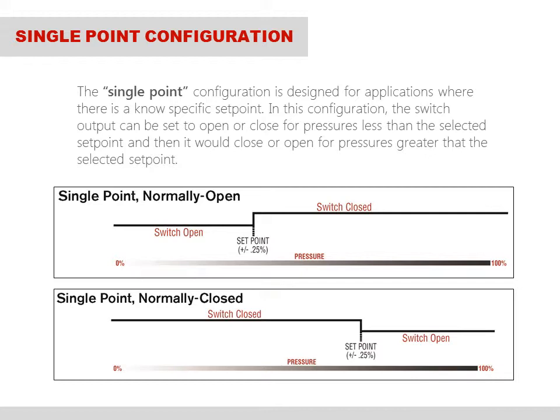The single point, normally closed switch functionality is best understood using the terminology open on rise, close on fall. In this case, at 0% pressure, the switch is closed or on. It remains closed until the pressure rises to the set point, at which time it opens or turns off, and remains open until the pressure decreases or falls back to the set point, at which time the switch returns to its normally closed condition.